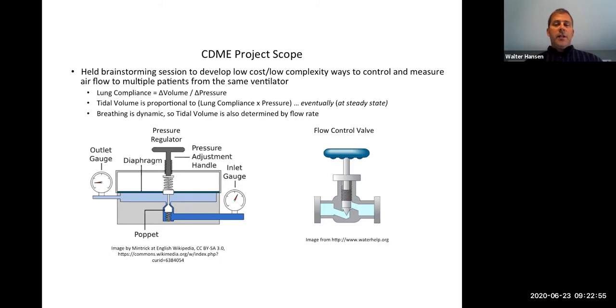But breathing is dynamic, and it takes time for the lung pressure to equalize to the supply pressure. That means the volume of air with each breath, the tidal volume they receive, is also determined by the airflow rate. This is important because it let us simplify our control mechanism from pressure control to flow rate control. On the bottom of this slide, you can see schematics of a simple pressure regulator and a simple flow control valve. You'll notice that the pressure regulator requires several extra components that make the design and manufacturing more complex and expensive than the comparatively simple flow control valve.